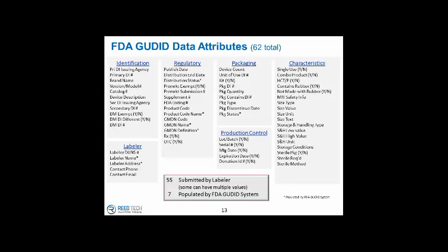That's a good question. So this is one of those subtle format issues. When the data is sent to the FDA, the actual requirement of the FDA is a lowercase true and a lowercase false. So when you're working inside a system collecting that Boolean field, depending on what system you have, you may be using yes and no, you may be using a 1 or a 0, you may be using a Y or an N or a T or an F. Ultimately, the system that generates the messaging to the FDA needs to use lowercase true and lowercase false.